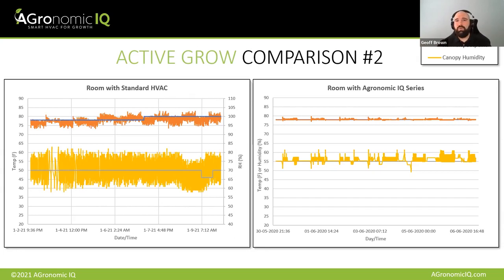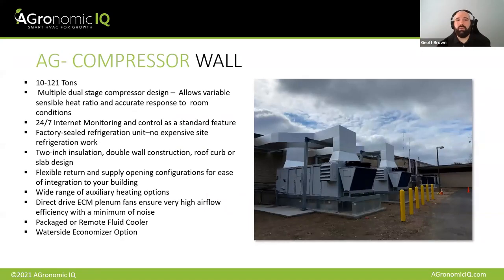And so the rooms that we're seeing here are treated by our flagship equipment, and that is the compressor wall units. If you guys are familiar at all with fan arrays or that kind of concept, we've basically taken that and applied it to compressor circuits instead. So instead of having a couple of large compressor circuits, we've got many small compressor circuits, and each one of those compressor circuits is still served by a two-stage compressor. So you end up with a lot of stages of control available in these, which allows them to tailor themselves very nicely to the room demands.